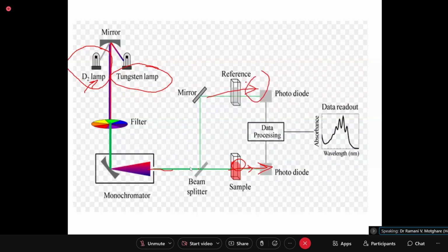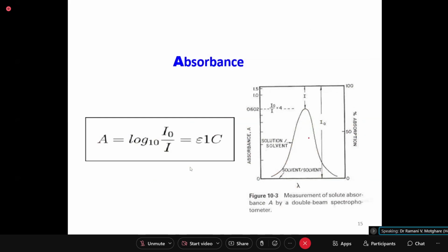So if you measure the difference between this quantity of transmitted light and this IT, then you will get to know how much is the absorbed quantity. This minus this value will be the absorbance, and that is what is measured by this. If it is a continuous one, you get all the values for different wavelengths, depending on your spectrophotometer. The wavelength at which a colored solution absorbs maximum light is termed as lambda max, or wavelength of maximum absorption of light.